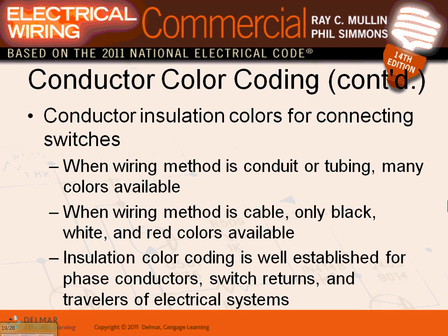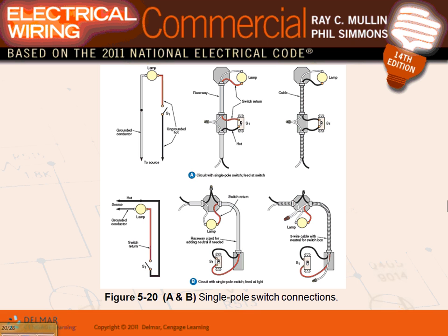Use conduit or cables. Black, we talked about the color return. If you're using, guys, a cable, only cable, not conduit. If you're wiring with cables, can I wire with cable in an MC cable in a building like this and bring the power to the switch and out of the switch? Yeah. If you're using the switch as a cable bringing power to the switch and out of the switch, then the one that brings power to the switch has to be always the re-identified white conductor. We did this in the residential, guys. You remember the re-identified grounded conductor?